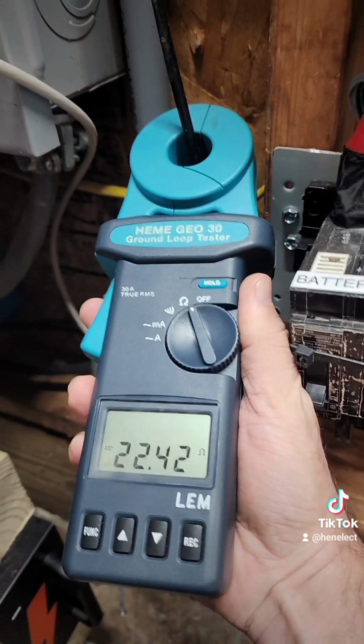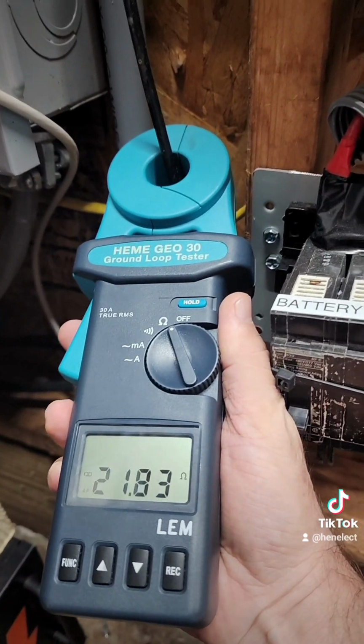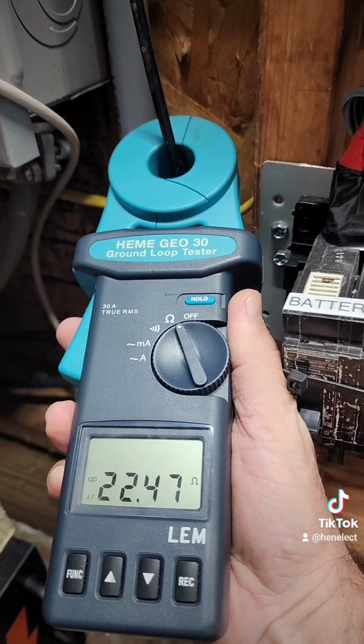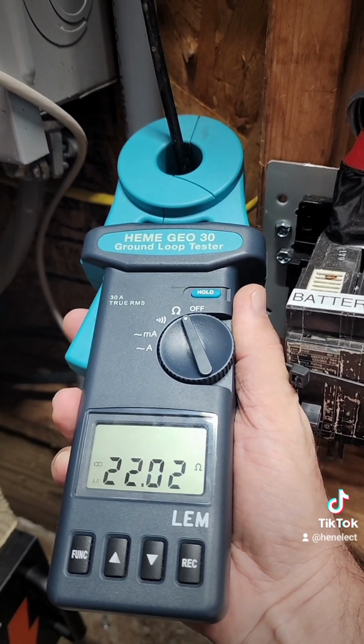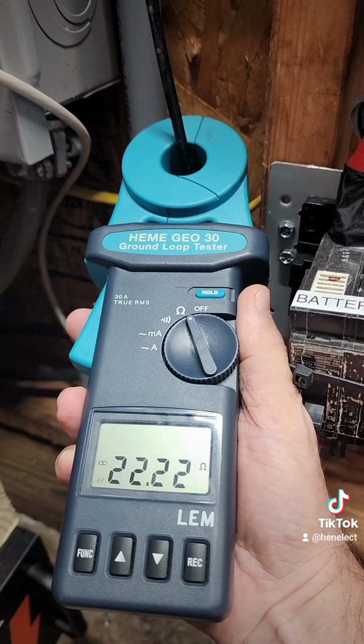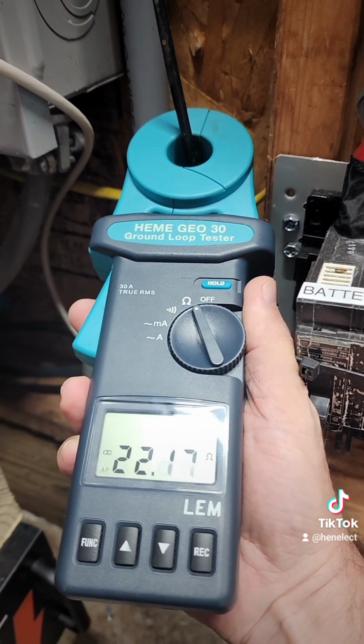So what I'll do now is just clip it around my meter. Now, you don't even have to put test on this. So I have, as you can see, 22 ohms to ground. It's actually not too bad. That's a pretty good ground.